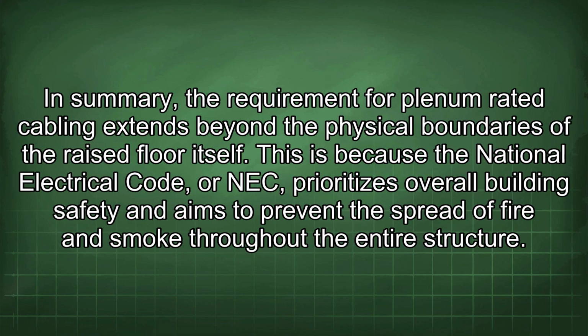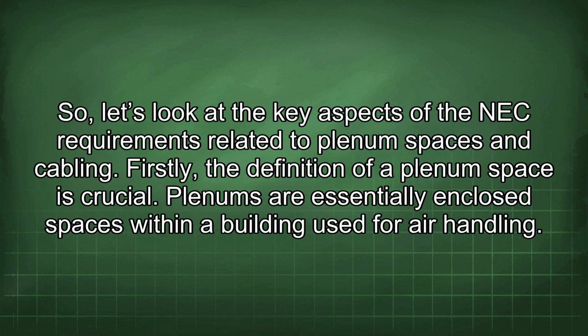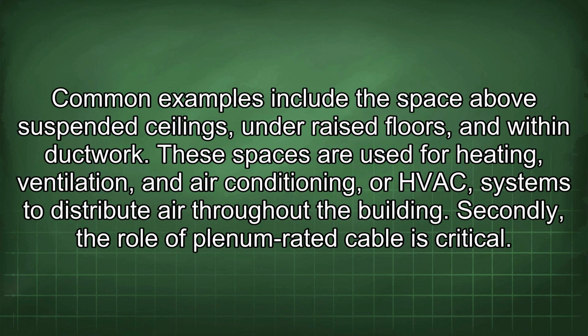In summary, the requirement for plenum-rated cabling extends beyond the physical boundaries of the raised floor itself. This is because the National Electrical Code, or NEC, prioritizes overall building safety and aims to prevent the spread of fire and smoke throughout the entire structure. So, let's look at the key aspects of the NEC requirements related to plenum spaces and cabling. Firstly, the definition of a plenum space is crucial. Plenums are essentially enclosed spaces within a building used for air handling. Common examples include the space above suspended ceilings, under raised floors, and within ductwork. These spaces are used for heating, ventilation, and air conditioning, or HVAC, systems to distribute air throughout the building.